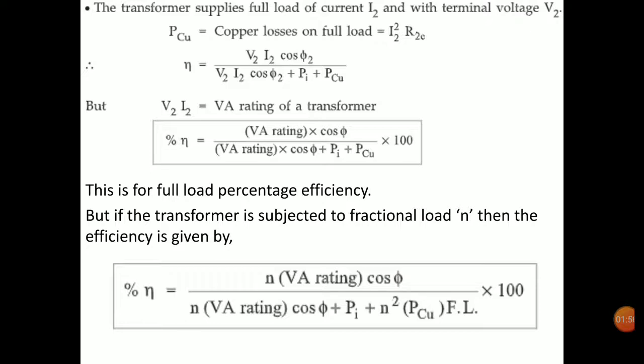If we are operating the transformer at a load other than full load, this formula doesn't apply. The formula for efficiency at any fraction of load is: percentage eta equals n times VA rating times cos phi, divided by n times VA rating times cos phi plus Pi plus n² times Pcu full load. Here Pcu full load refers to the full load copper losses.